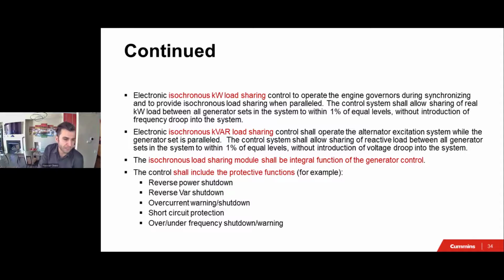And also we need to have some kind of a level of protection as well. I've listed in one of the slides the elements and the ANSI designation, and those are the most common elements that you want to have on a genset when you're paralleling generators together. Those are the most common points that you want to have for protection. So again, reverse power, reverse VARs, overcurrent, short circuit protection, obviously, and then under voltage and a few others that I didn't list in here just for space, and we don't have the time to discuss them all.